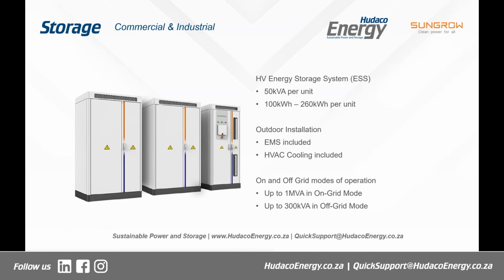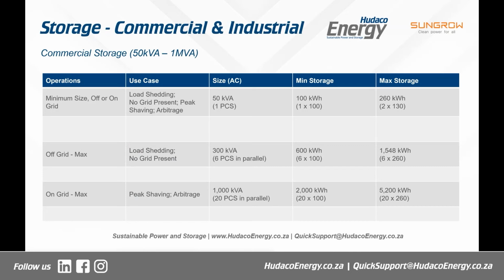If we go to the next slide, we can see each building block is 50 kVA with a minimum storage size of 100 kilowatt hours going up to 260 kilowatt hours. And this operates in both on-grid and off-grid mode. So in other words, you don't have to add any new hardware to either provide backup power during load shedding or to do peak shaving or arbitrage. It's the same system. It just moves from off-grid mode to on-grid mode.